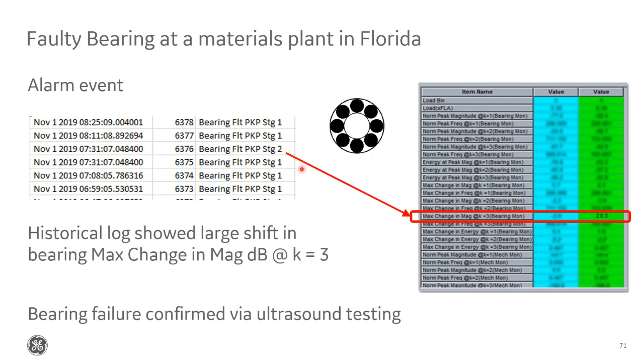So they went back, they looked at all the records. They saw this max change value was somewhere around 20 decibels in their historical log. This is what the relay picked up on. And then when they actually did an ultrasound test, they found that there was a very small crack in one of the bearing balls. So the 869 ESA option caught a failure that wasn't even noticeable to the eye. So we were able to catch an incipient fault successfully.